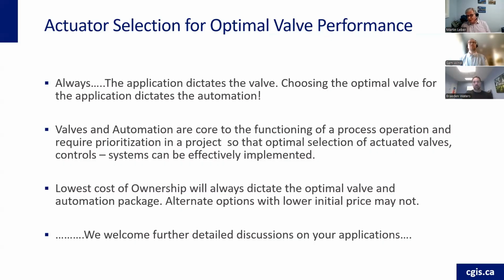The electronic series actuators have that feature built in for loss of control — if you lose your supply power, it will not be able to do that. The hardwired series actuators do not have that option. So there are ways to get around this, using battery backup systems to drive your actuation. The electronic series has a fail last, fail close, and ESD option where if certain conditions are met, the actuator will close on its own. However, if you lose the three-phase supply power, it will not be able to close.